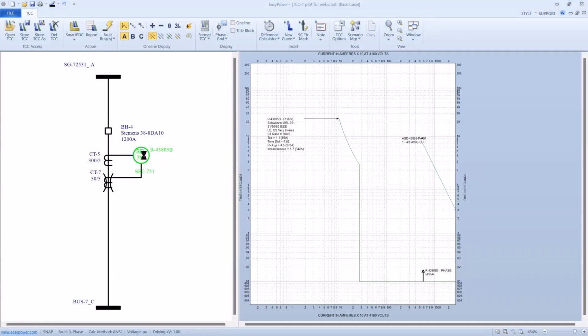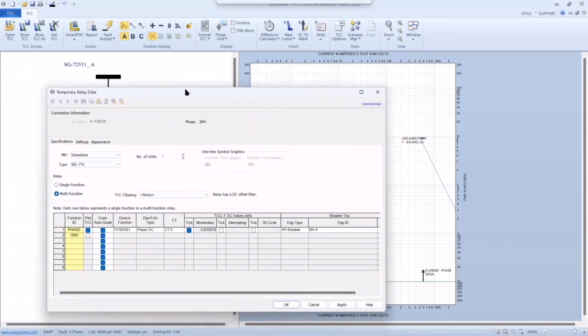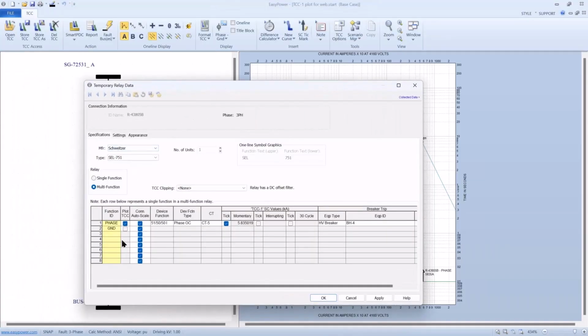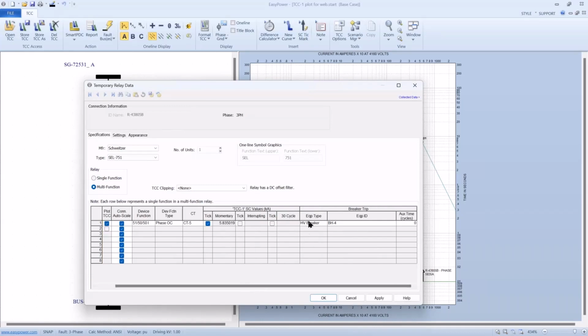If I open up the relay icon, I can see the setup. We're looking at the phase trip. Now I want to point out that even though the tool makes a pretty good estimation of what breaker it's going to be activating, if I left this blank, it would still probably find BH4. My recommendation is to make sure you've designated this, especially in a relay-rich environment, because there can be misdirection. The same is true for the CT, especially if you have multiple functions on the same relay and multiple CTs, you could get cross-pollination between ground.